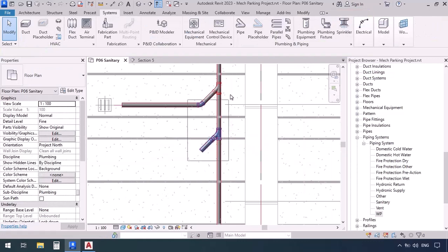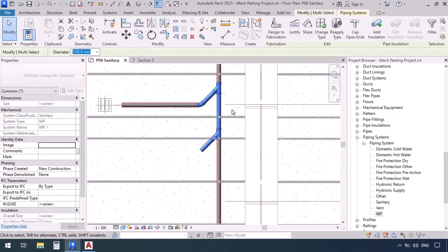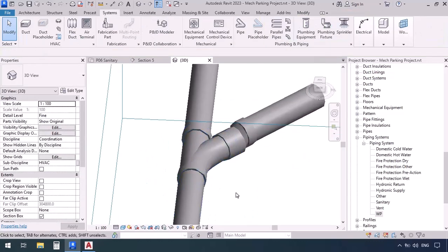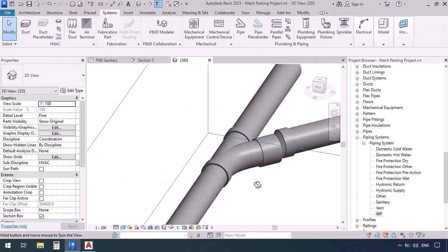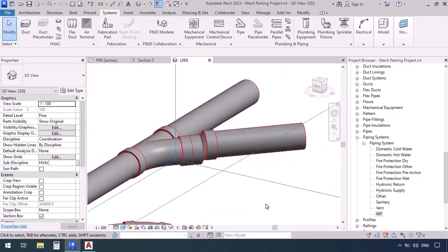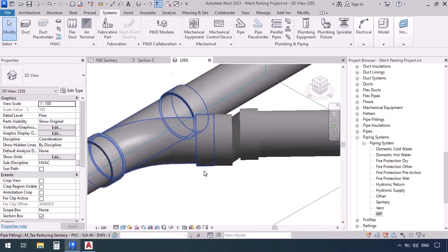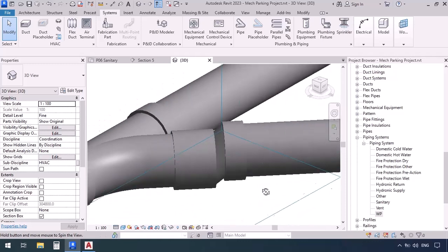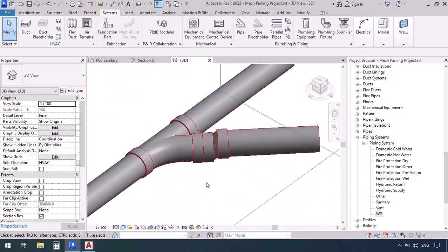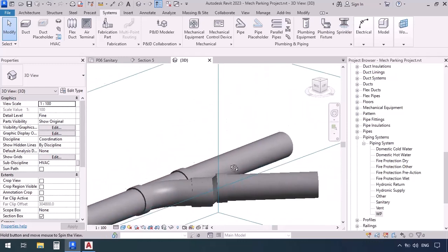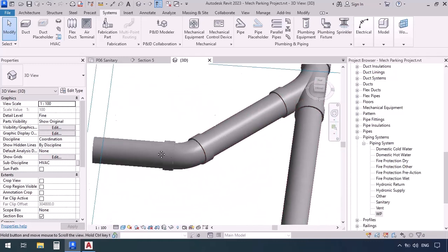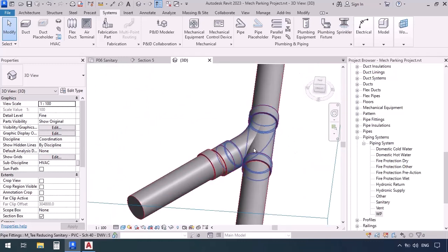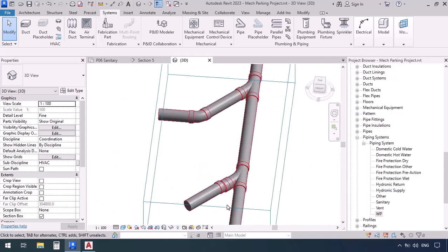Let's go check it out in 3D. I'm going to drag to select them, then click on Selection Box so we can only see this part in 3D. Do you see how it looks? It looks a little tilted — kind of like it had no choice but to connect these pipes together. In order to do that, it placed a reducer. This reducer doesn't mean it reduces the sizes; it was just the software's way of showing the change in elevations. When we viewed it in 3D, we saw that it was all wrong.